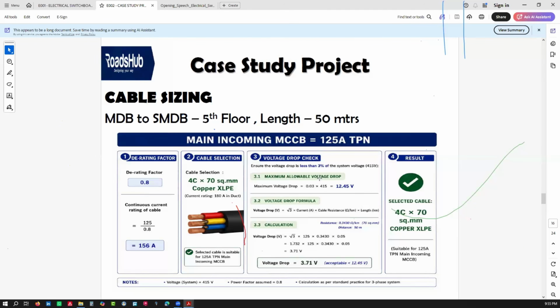So you know your maximum allowable voltage drop. For most distribution systems, if the voltage drop is above 3%, we have an issue. So if it's a three-phase system, you have 3% of 415, you get 12.45. So every test needs to have a value below 12.45 for it to pass. So if you do the math, this is √3 × current × cable resistance × length.